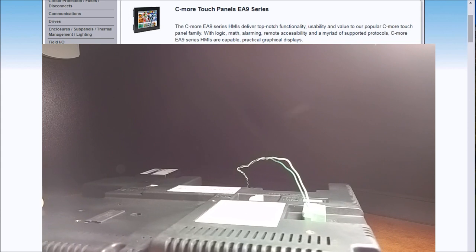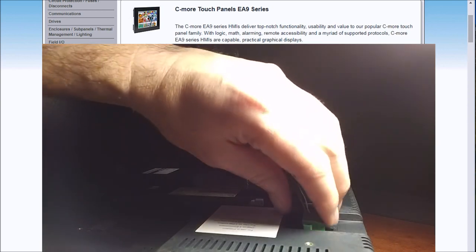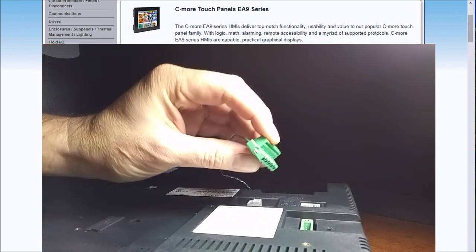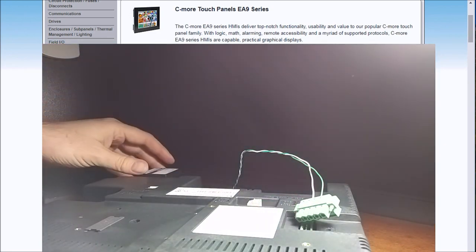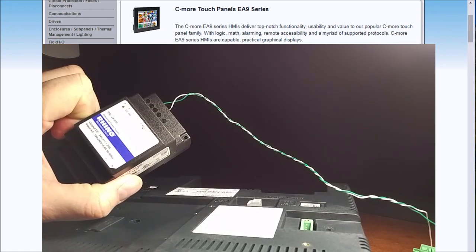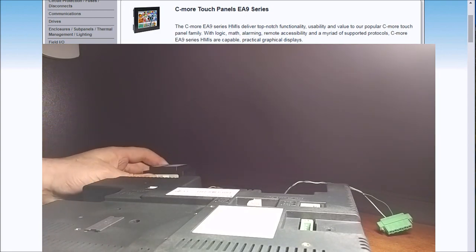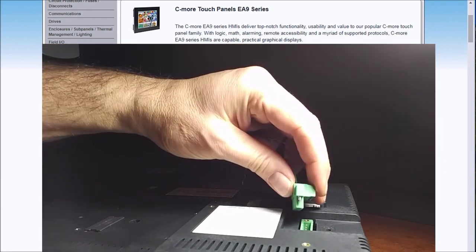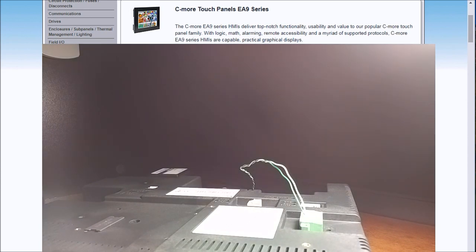It's a T10CL. I flip over the back here, and what we'll find is that we have our connector located right here, and we can just pop that connector out. It provides 12 to 24 volts. And I have a Rhino power supply here, which is rated for a couple of amps. So it's actually 2.5 amps that is recommended for powering this unit up, based on all the different parameters we have in it. So positive on positive, negative on negative, and then we power this unit up.